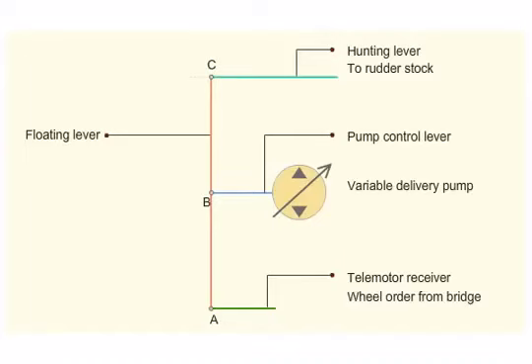One end of the floating lever is connected to the hunting lever and the other end is connected to the telemotor receiver. The pump control lever is connected to the middle of the floating lever. When the pump control lever is in B position, the pump will not discharge.